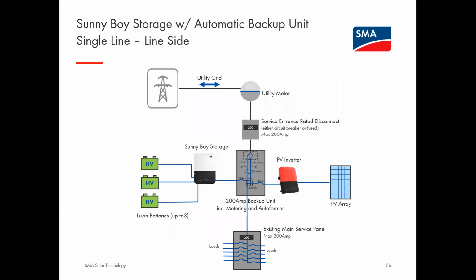So here are a couple of examples of how you can integrate the automatic backup unit in SunnyBoy Storage into the home. First of all, this is a scenario where my utility meter is not co-located with my existing main service panel. And that's fairly typical for homes on the East Coast, where generally the utility meter is at the street level and your main service is either in a garage or in a basement.